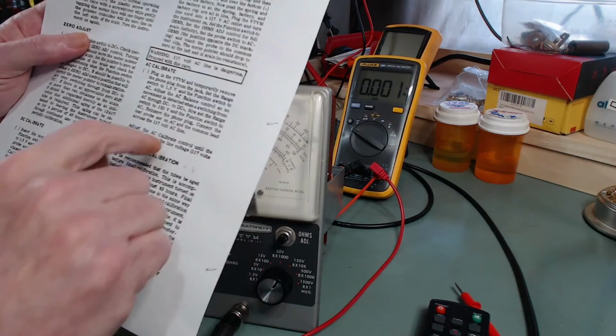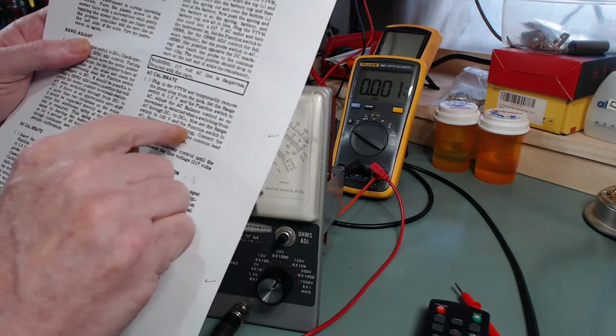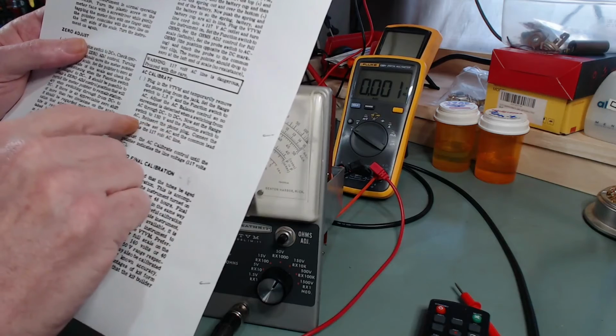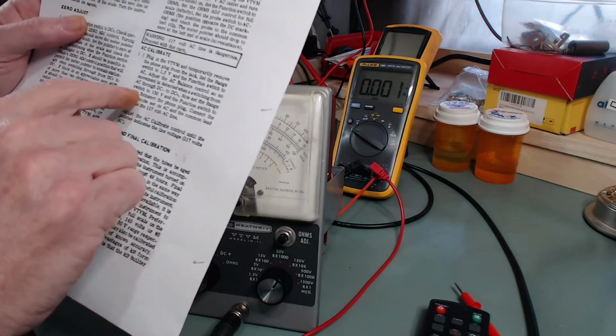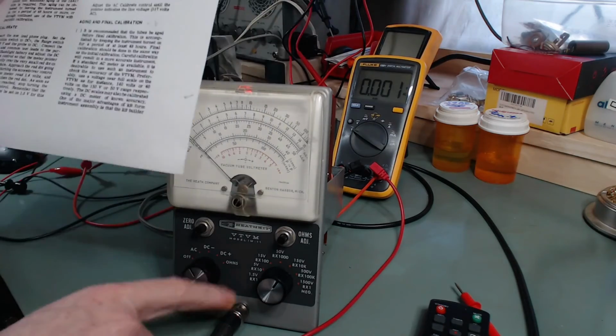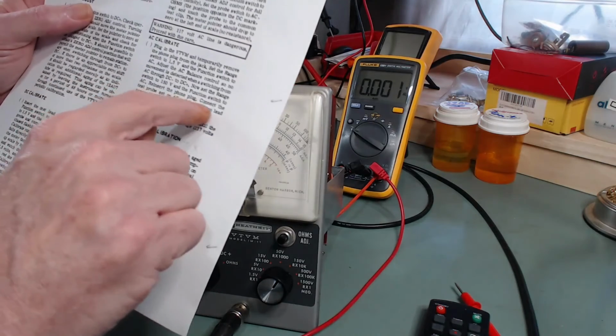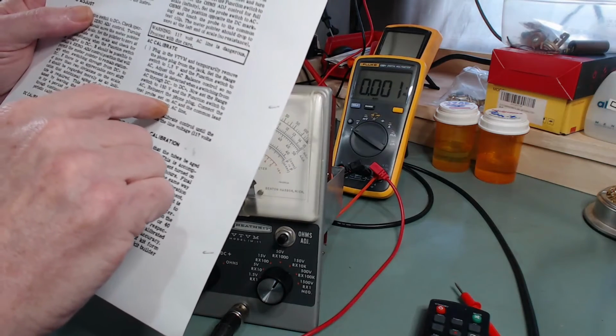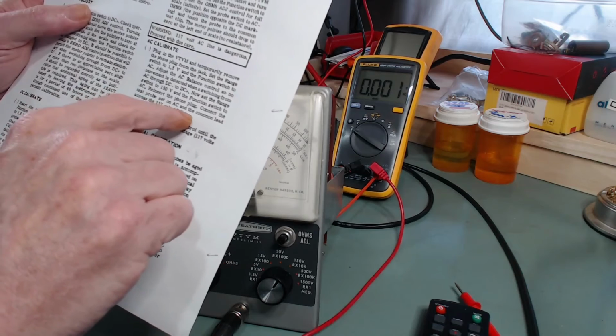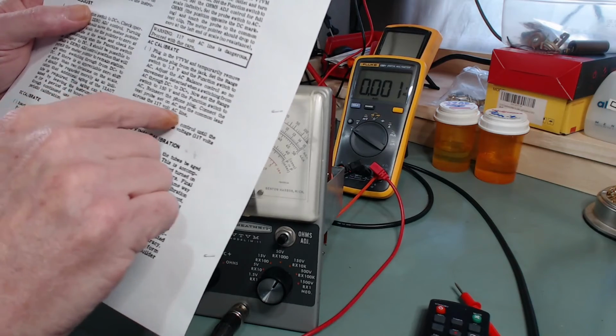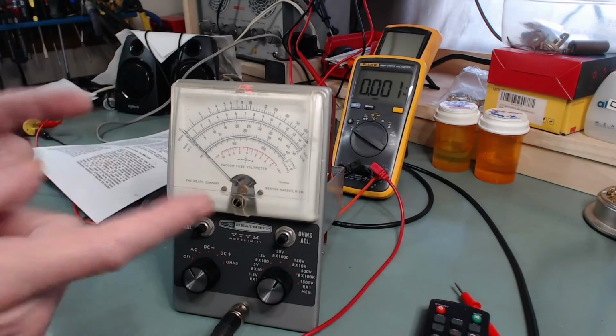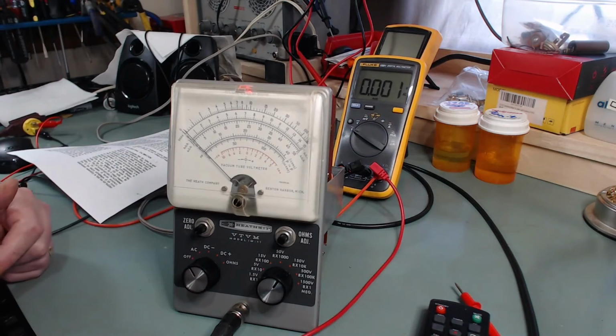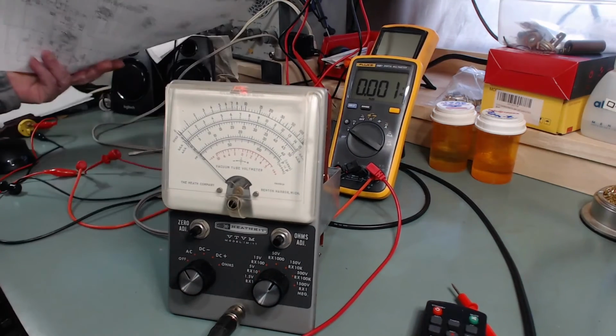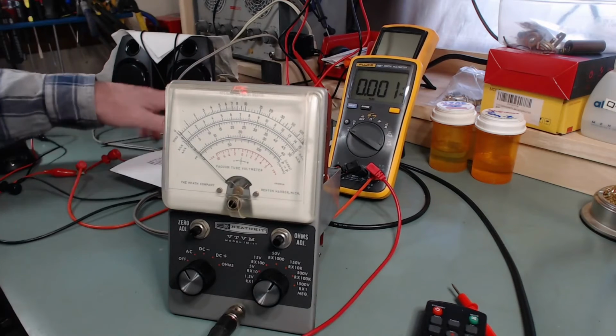Now here's where you need to be careful. Set the range switch to 150 volts and the function switch to AC, which it already is. Reinsert the phone plug, or in my case the BNC, and connect the test probe set on the AC to the common lead across the 117 volt line. So basically they're telling you to take the probe and plug it into the wall socket. And normally that would be a fairly dangerous thing to do.